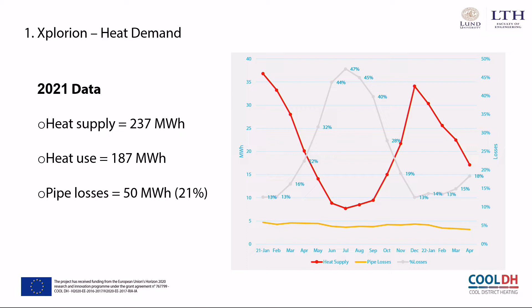And overall pipe losses in last year was near to 21%. Annual pipe losses was 13.9 kilowatt hour per square meter, while the reference value was 10.2 in the initial simulations. The reasons were, the first reason was that, as I explained, it's high return temperature, that it was fixed. I think the arrows is in the right place now.